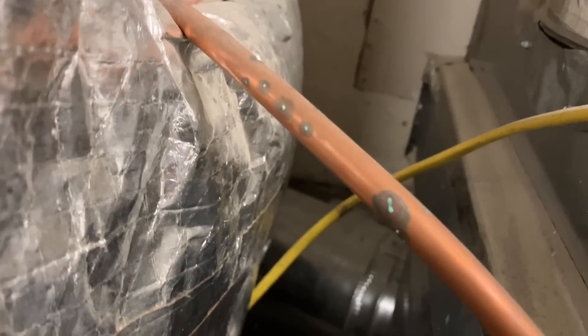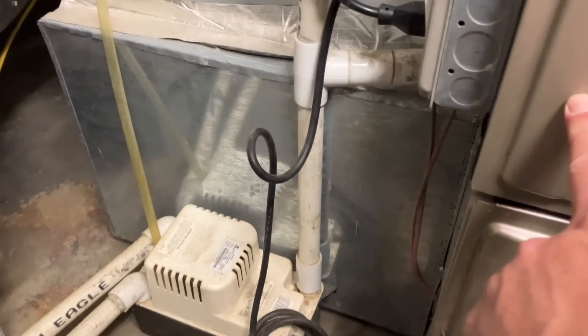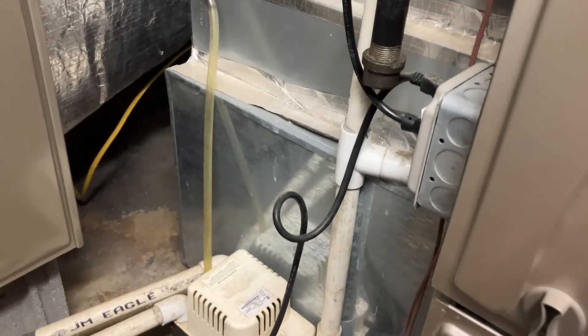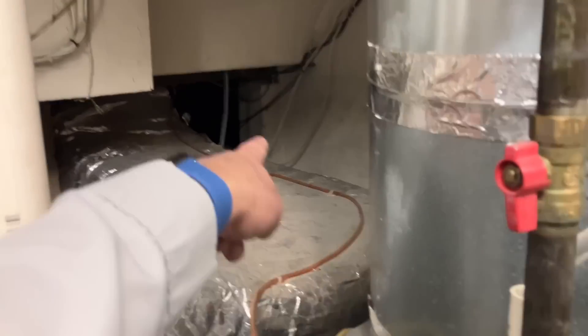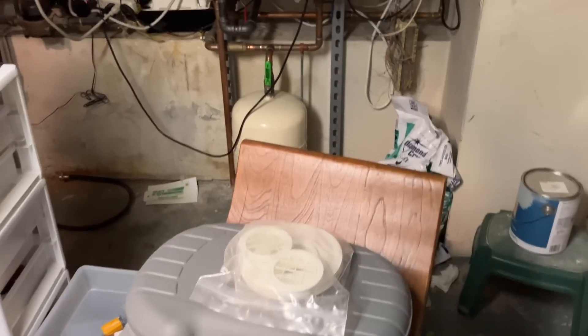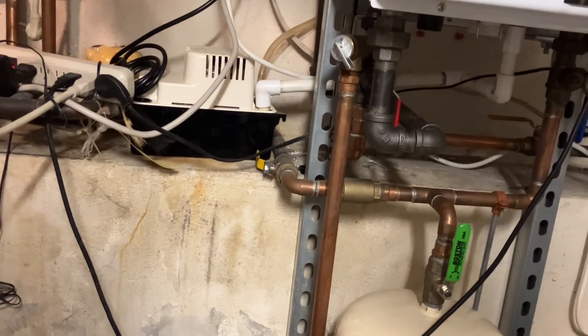The condensate pump serves the humidifier and the condensate coming from the heat exchanger. It looks like it's going into a copper tube, and I can guarantee you this one is going to get pinhole leaks in the copper — you're already starting to see it. The condensate that these 90-plus percent efficient furnaces produce is very acidic, and if there's any copper or brass in the discharge piping, it's going to rot out. I don't want to touch it because we'd accelerate the wear and tear process.